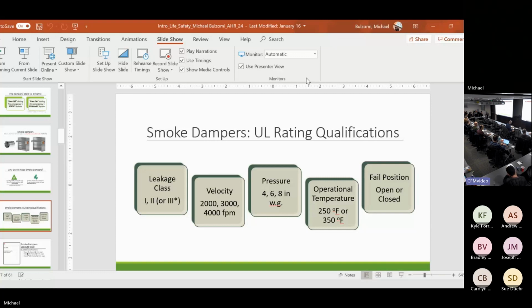Velocity and pressure now. Because a smoke damper is controlling the movement of smoke, the movement of air, they're dynamic. They have an actuator, they're dynamic. So there's going to be a minimum velocity and pressure rating. The standard is 2,000 at 4 inches. 3,000 and 4,000, 6 and 8 are what we call extended velocity and pressure ratings.